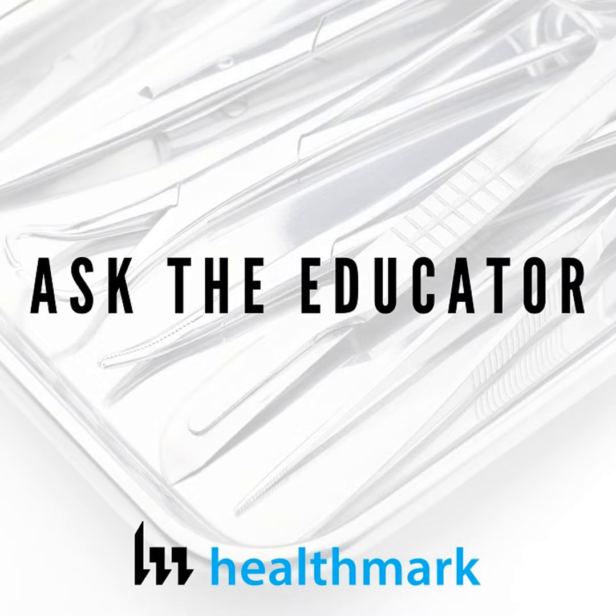Well, one of the things that I point out in the webinar is that there are studies out there. Dr. Alpha did one where she talks about and basically proves that manual cleaning methods are generally less effective than automated ones. And this was in particular with lumen cleaning devices. And so we have an advantage in that if we're already putting something in the ultrasonic cleaner, we should be using that lumen cleaning function. However, if it's not working properly, you're not getting the benefit of that automated cleaning.